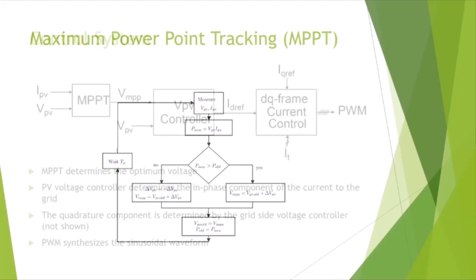So the simple control block diagram at a high level is shown here. You measure voltage and current, and the maximum power point tracking algorithm tells you the ideal voltage. You compare that ideal voltage with the actual voltage, and then come up with the ID reference. ID is the component of current in phase with the grid voltage on the AC side of the inverter, and IQ is the quadrature component. So the PV controller comes up with the desired reference current.